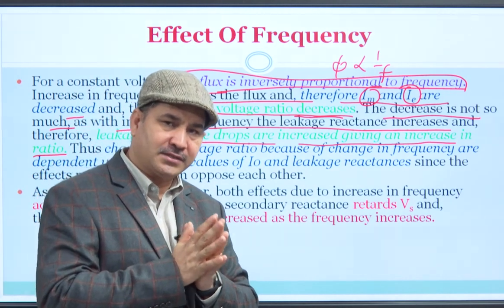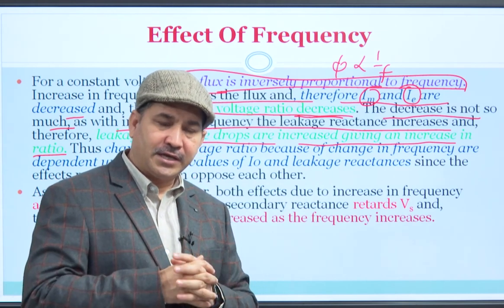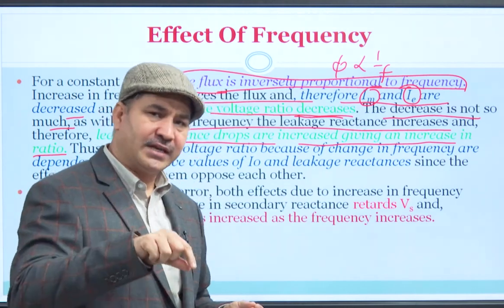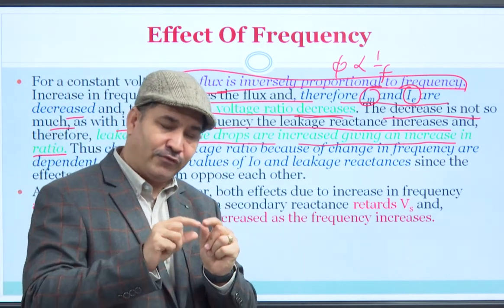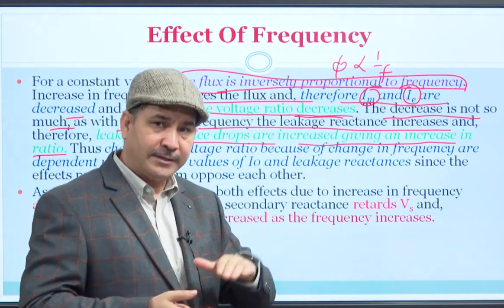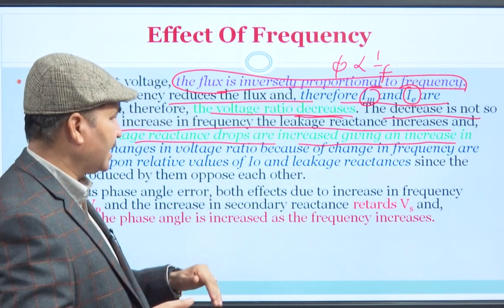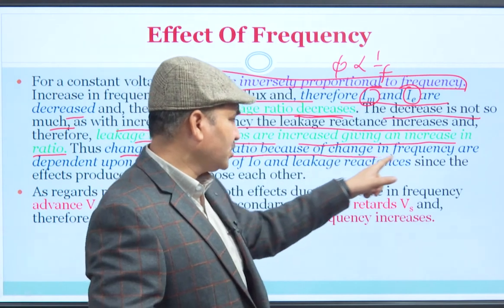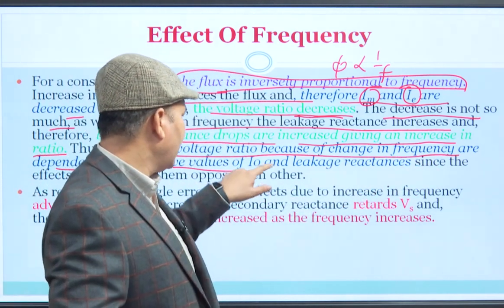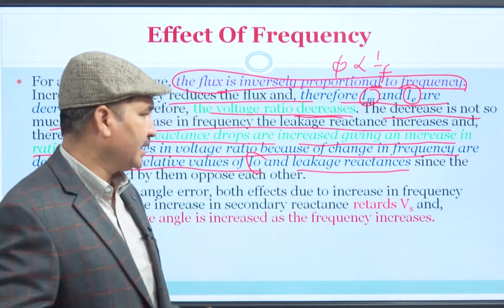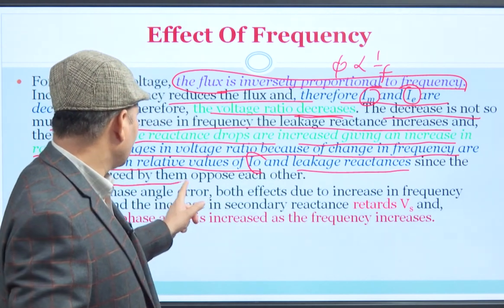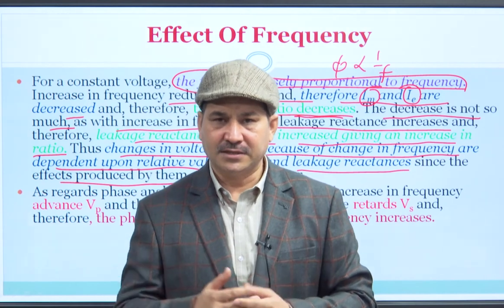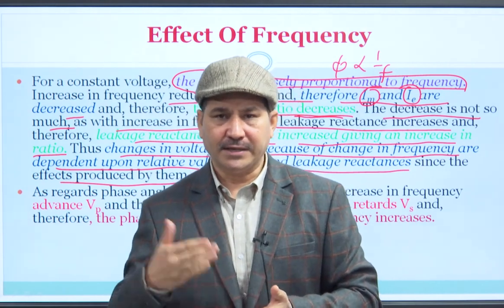This is an important point to remember: in the case of instrument transformers, it is desired that you operate them at rated frequency so that frequency variation is not much. The change in voltage ratio due to change in frequency is dependent upon the relative values of I₀ and leakage reactance. Since these effects oppose each other, they nullify the effect of frequency. Nonetheless, it is recommended to operate them at rated frequency, as the frequency does not have a major effect.